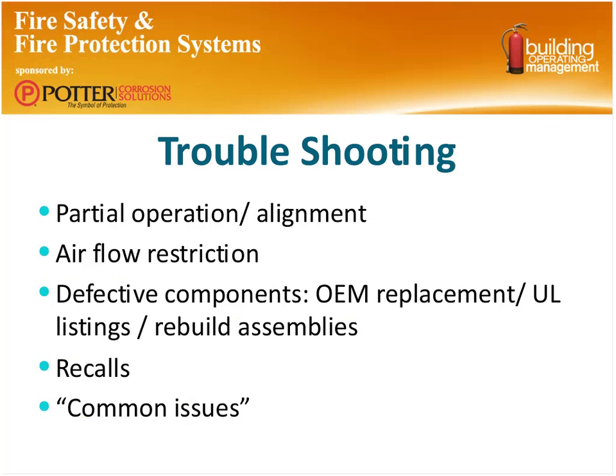So what are some of the typical problems that we find on dampers, fire dampers and smoke dampers? Well, one of them, misalignment, things that have gotten cockeyed and just don't operate completely. Two, airflow restrictions. Three, I'll bring up the point that if there are defective components found during the inspection and testing, by code today, all damper parts have to be replaced with original OEM replacements. Otherwise, if your motor burns out, you can't just put a generic motor on it. It has to be the exact motor that was on that unit to begin with from the OEM. It can't be a third-party Grainger motor or some third-party site.